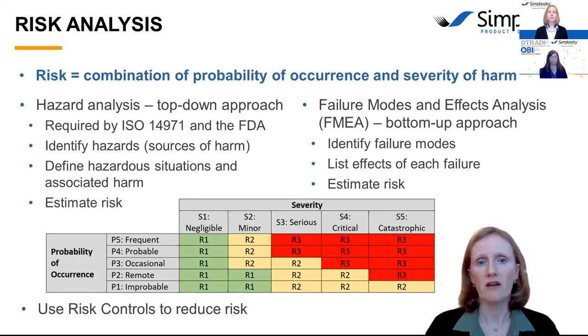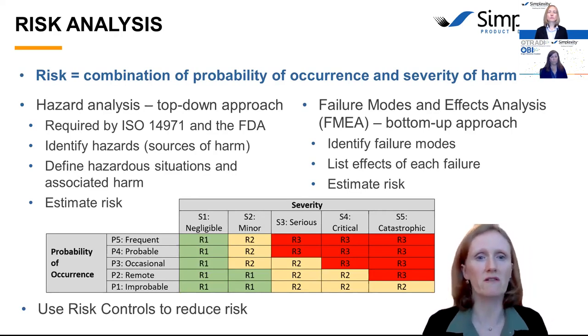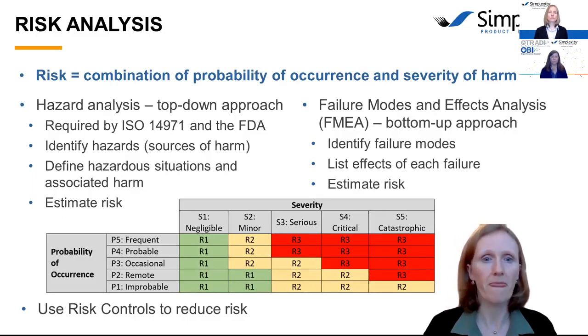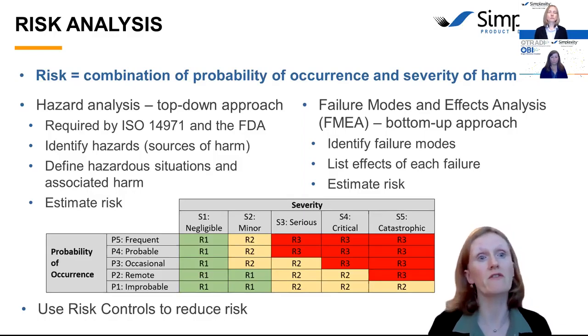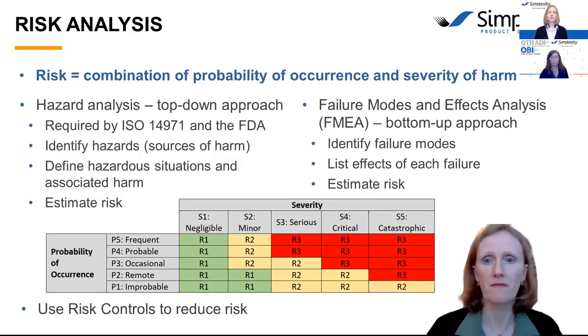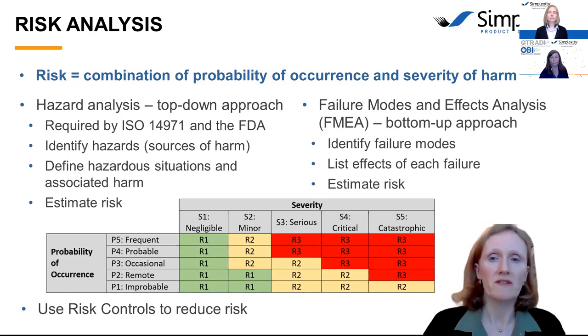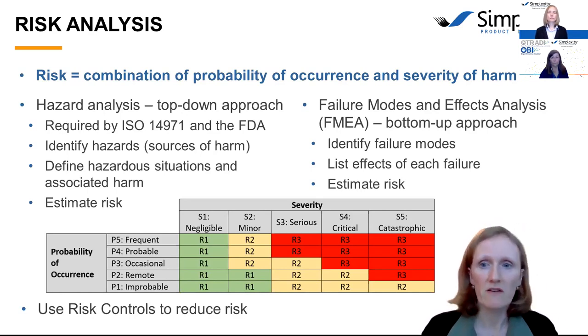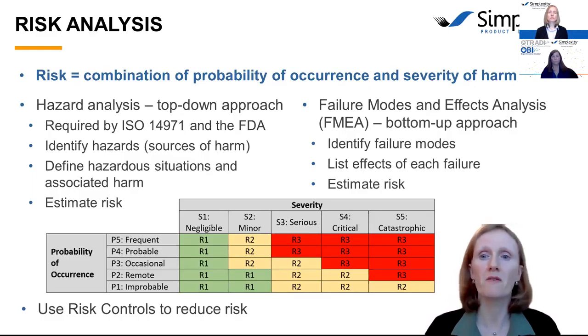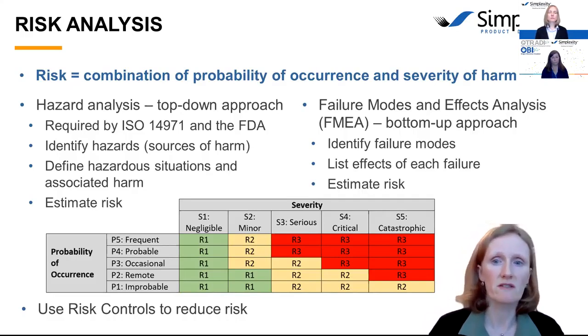In an FMEA, on the other hand, you start with your design. So you identify in your design where the failures could occur. And then you list the effects of each failure, and then you take that and estimate risk. One thing to note is that a hazard analysis is required by the regulations, whereas FMEA is not. The critical piece that's missing from an FMEA, but is present in the hazard analysis, is identifying the hazards and the harm. The FMEA identifies failure modes and calculates the risks slightly differently.